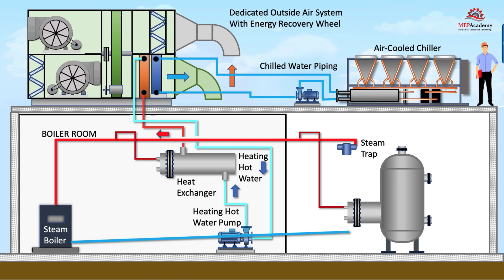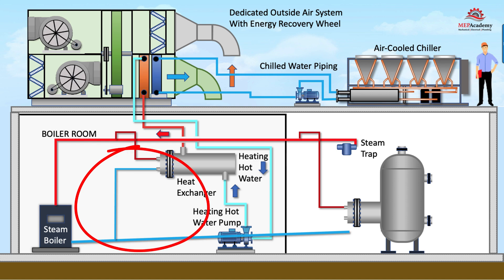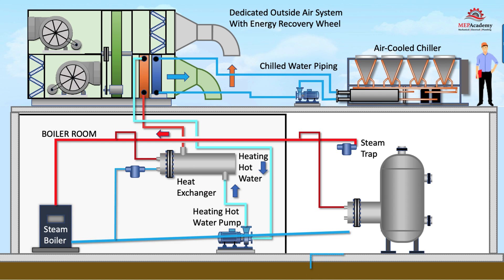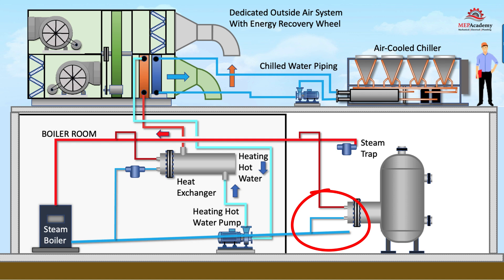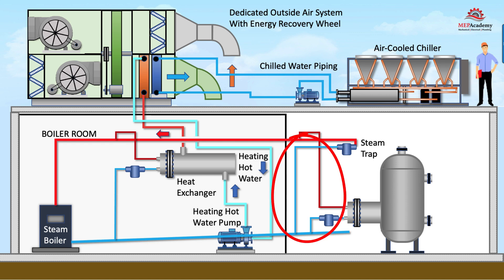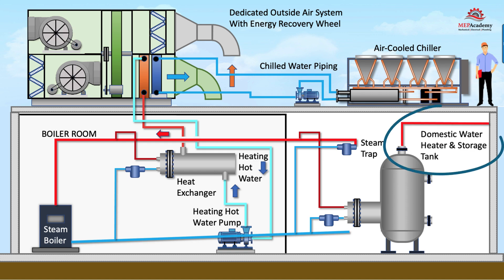A main condensate pipe needs to connect all the condensate from any steam systems. We'll connect the condensate from the heat exchanger to the main condensate line, being sure to install a steam trap to prevent steam from escaping — as allowing steam to escape would be a waste of energy. We'll also connect the condensate from the heat exchanger that feeds the domestic hot water system and include a steam trap. We then connect the steam main through the steam trap to the main condensate piping going back to the boiler, and feed the building with domestic hot water, including a return line and make-up water.